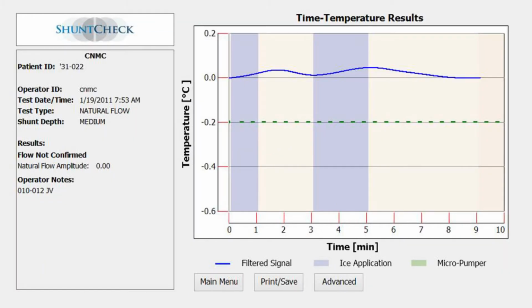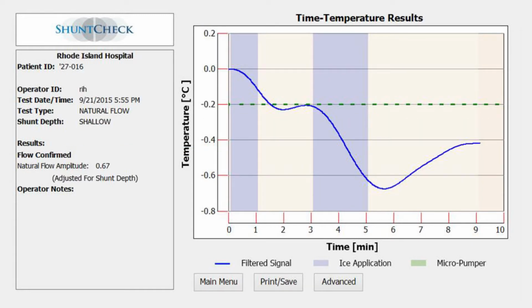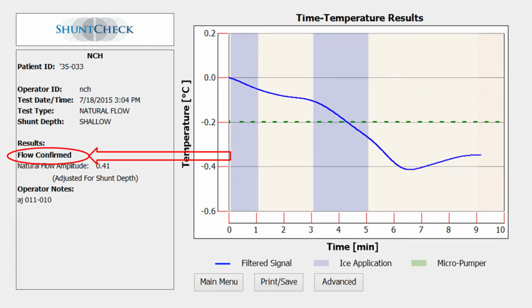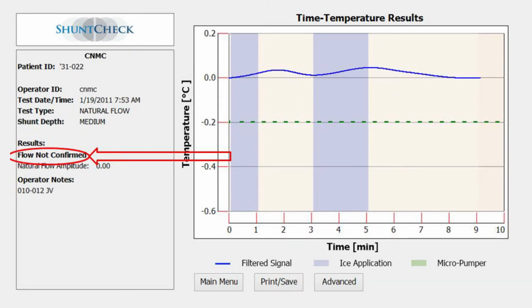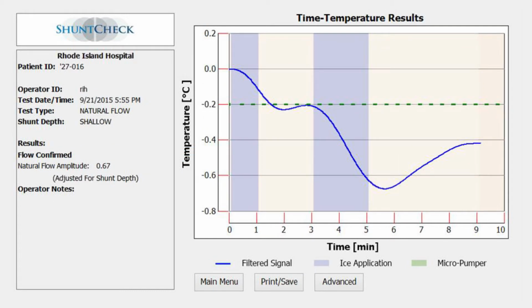This test shows no drop in temperature. Cooled CSF remained upstream and has not reached the ShuntCheck sensor, so ShuntCheck reports flow not confirmed. The temperature drop is a function of CSF flow rate. Faster flow, deeper temperature drop. This test shows a deep temperature drop, indicating very robust flow. So while ShuntCheck provides a binary flow confirmed or flow not confirmed result for each test, the time temperature graph gives a more granular sense of flow rate. Is it no flow, low flow, medium flow, or strong flow?